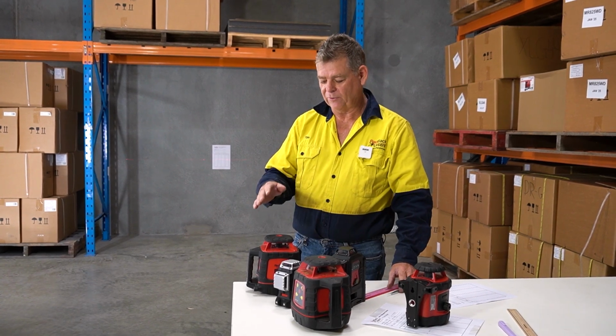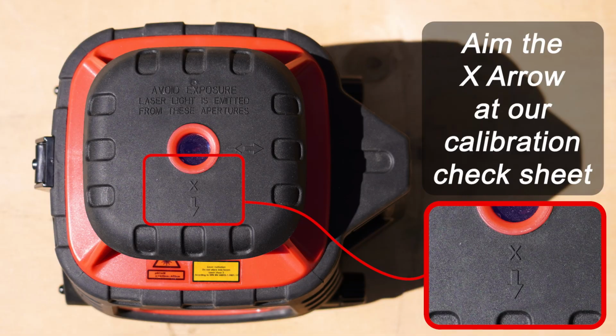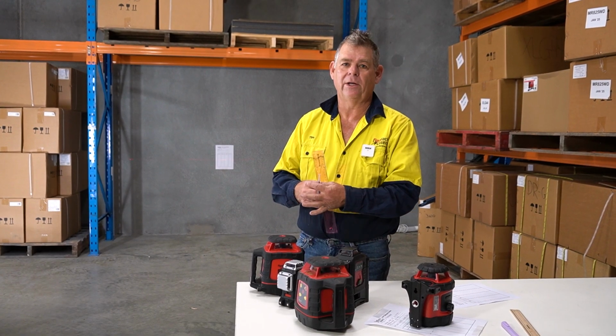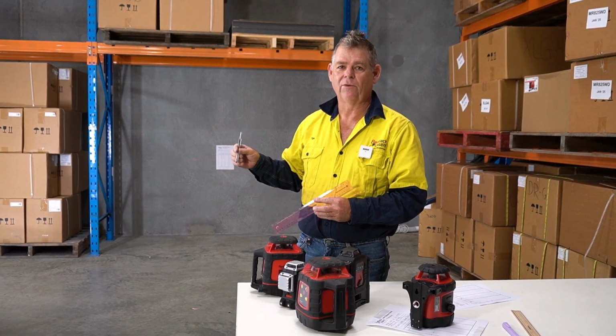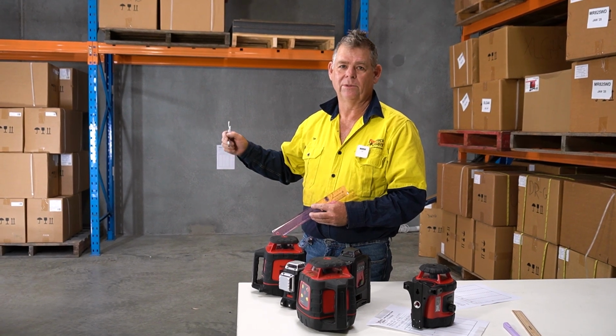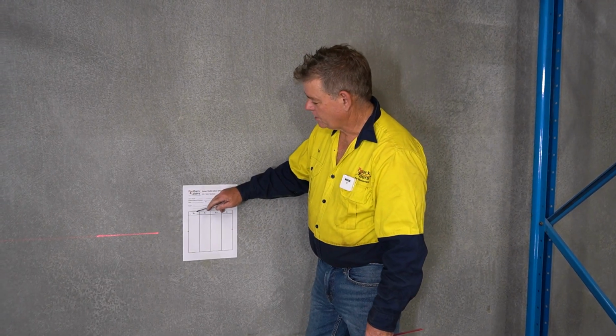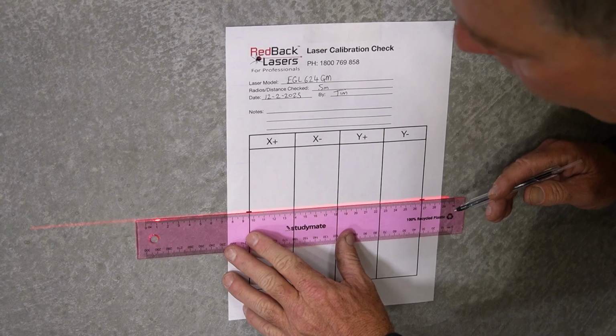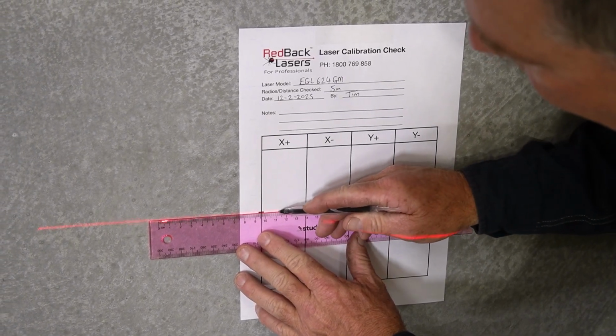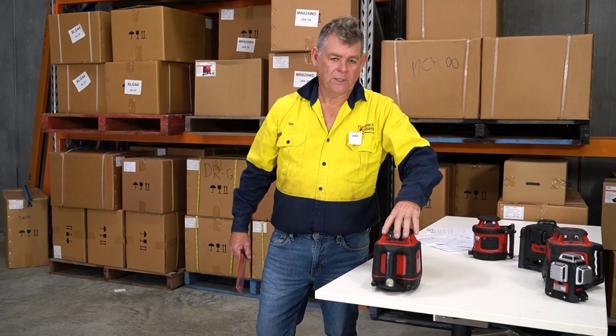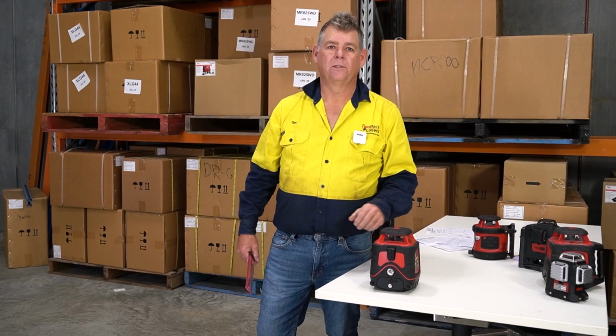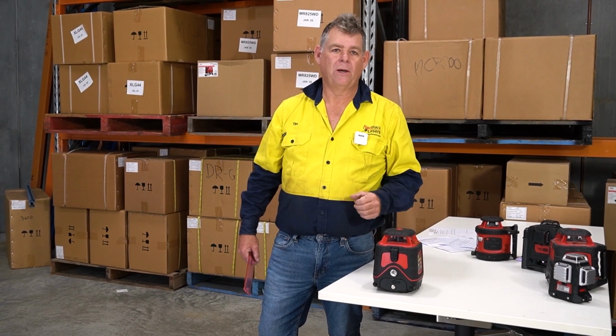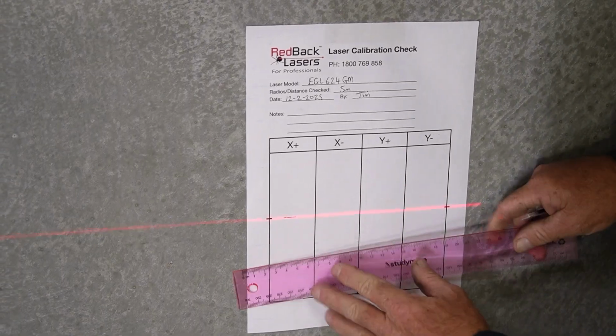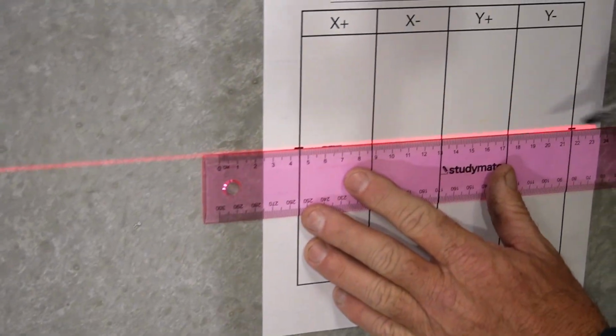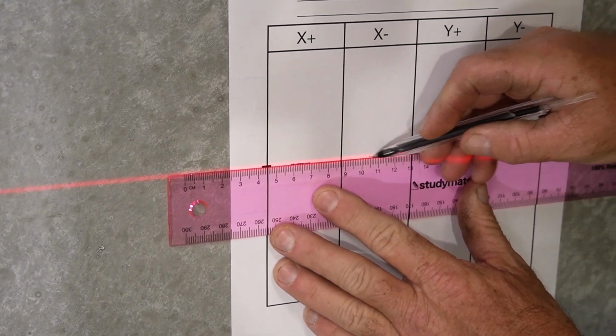Now with this laser, I've turned it on and I'm aiming the X arrow directly at my calibration check sheet. And what I'm going to do is go down there and mark in the X positive column where that laser beam's intercepting. So in the X positive column, we're going to put our ruler across there and mark about 1 centimetre along. So we're going to rotate that laser 180 degrees to bring up the X negative, aiming at our calibration check sheet. Again, we're going to put our ruler and do another mark of around 10 mil of where that laser beam intercepts.